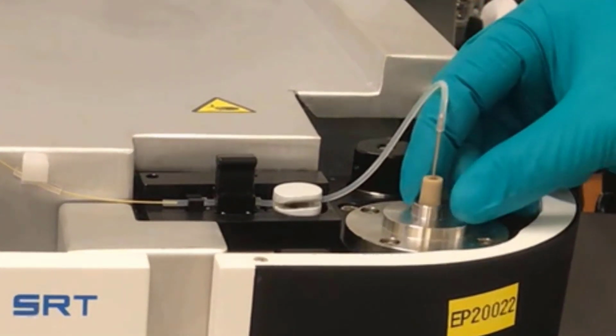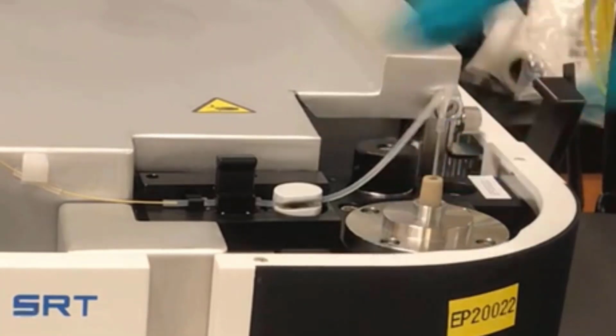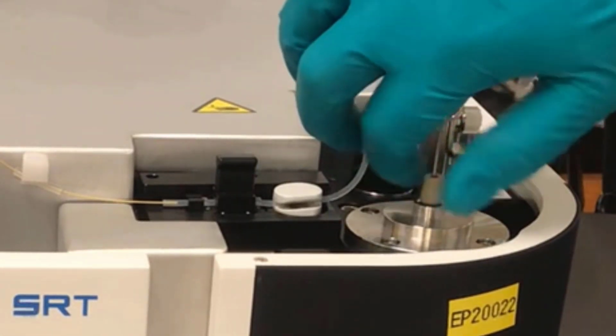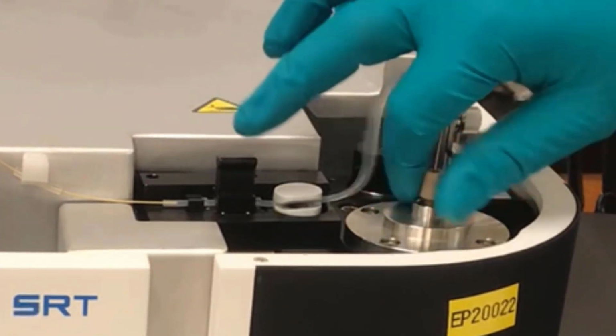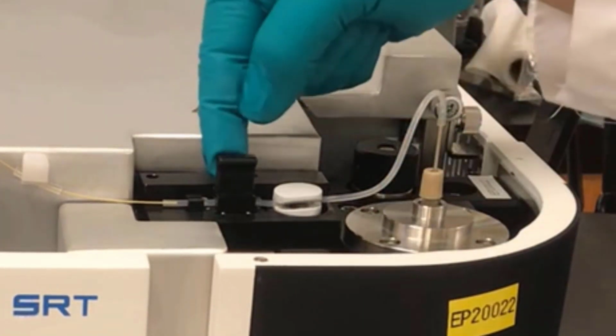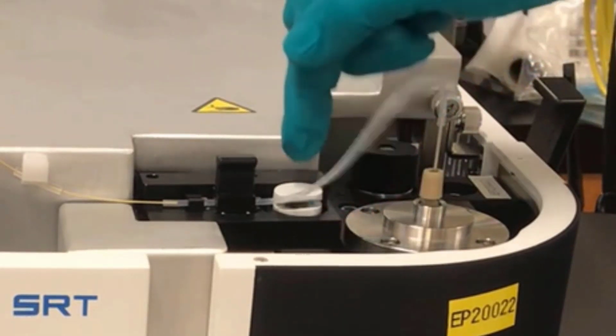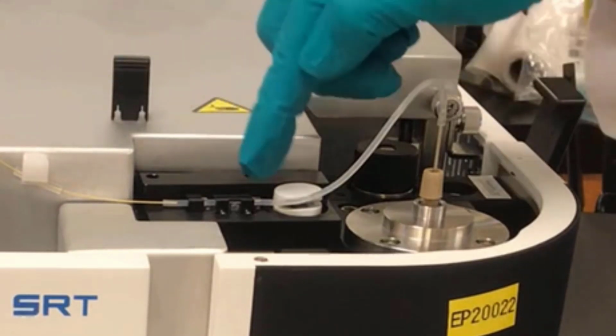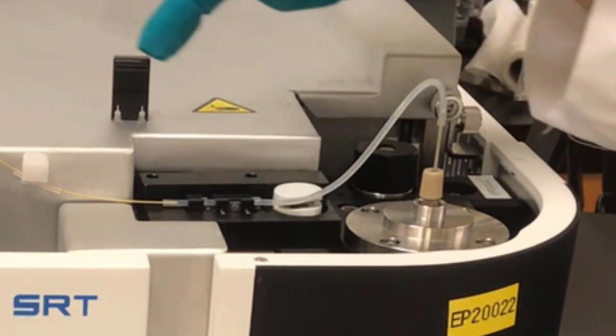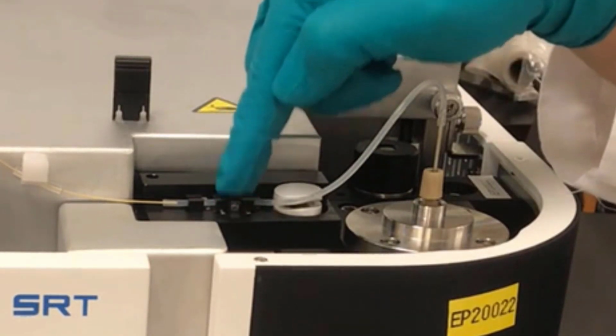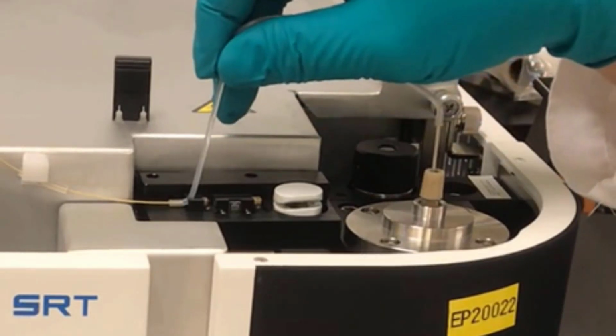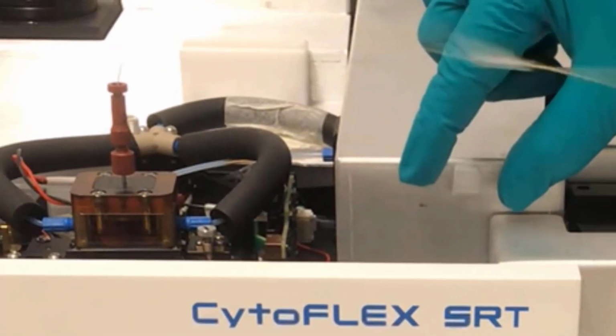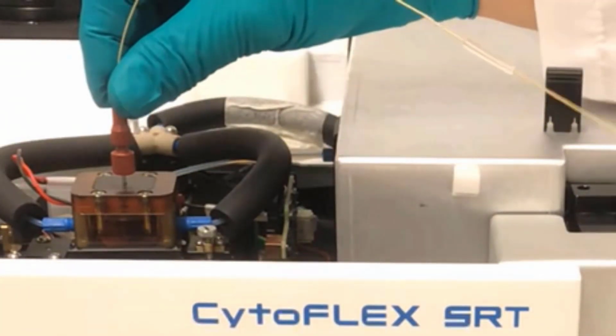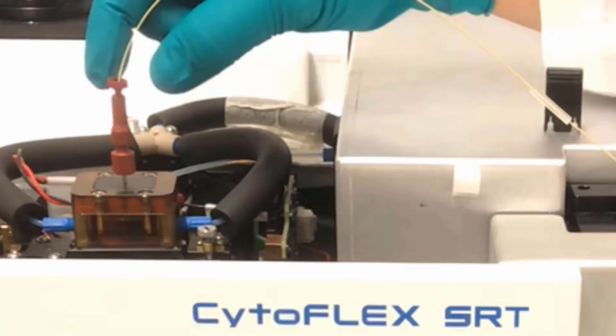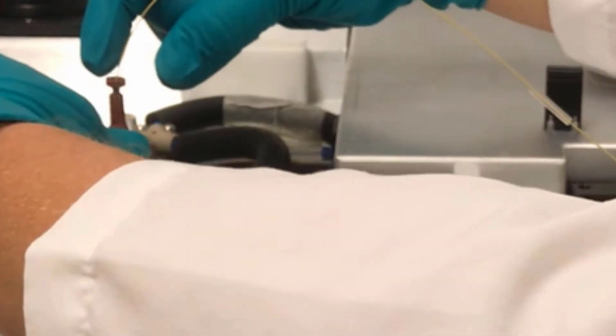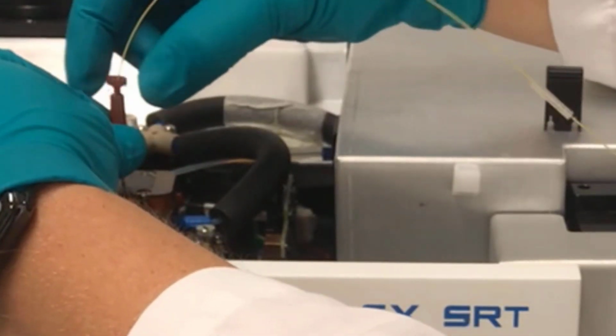Turn the gray finger tight fitting attached to the sample probe counterclockwise. Carefully pull the silicone tubing away from the sample line bubble detector and the pinch valve slot. Remove the sample line bubble detector cap. Hold the fitting adapter securely and turn the brown finger tight fitting counterclockwise to disconnect the PEEK tubing from the finger tight fitting adapter.